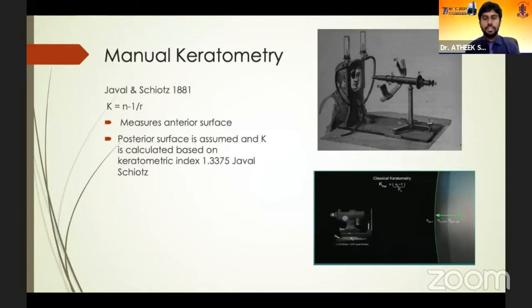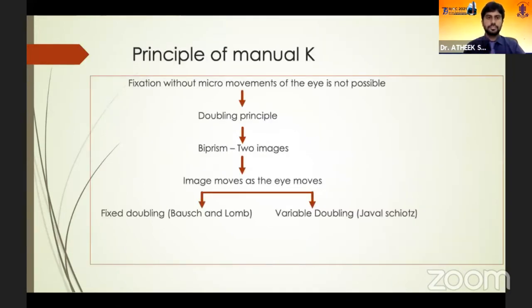Javal and Schiotz came out with the more practically usable keratometer in 1881, and this principle holds good even now — even the Bausch and Lomb keratometer uses a similar principle. In this keratometer, the anterior corneal surface is measured and the posterior surface is presumed, calculated based on a keratometric index. It works on the principle of fixed doubling, using a biprism to negate micro-movements in the eye.